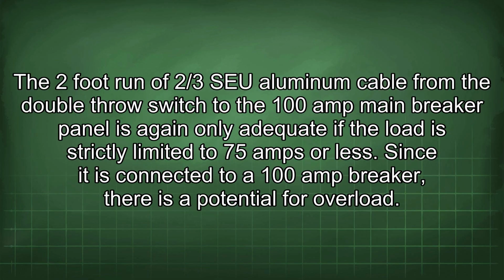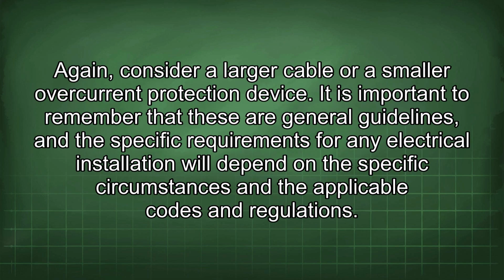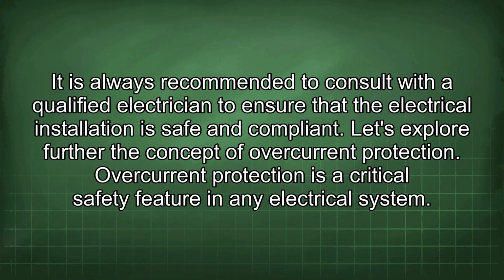The 2-foot run of 2/3 SEU aluminum cable from the double throw switch to the 100 amp main breaker panel is again only adequate if the load is strictly limited to 75 amps or less. Since it is connected to a 100 amp breaker, there is a potential for overload. Again, consider a larger cable or a smaller overcurrent protection device. It is important to remember that these are general guidelines, and the specific requirements for any electrical installation will depend on the specific circumstances and the applicable codes and regulations. It is always recommended to consult with a qualified electrician to ensure that the electrical installation is safe and compliant.